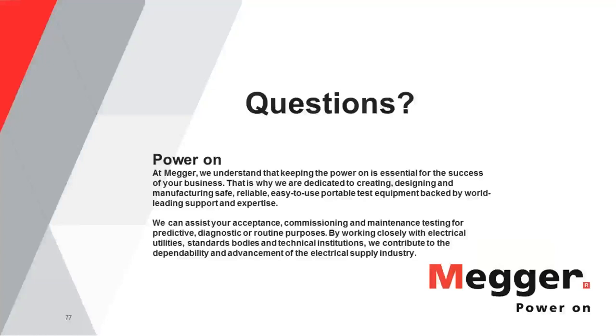All right, thank you, Volney. Next question is for Jeff. Can the temperature of the wire you are testing affect the results or measurements that your tester is giving you? Yes, it can. In fact, it's very profound, and it's one of the most fundamental things you want to take into consideration when you're doing insulation tests. The higher the temperature, the lower the insulating value.